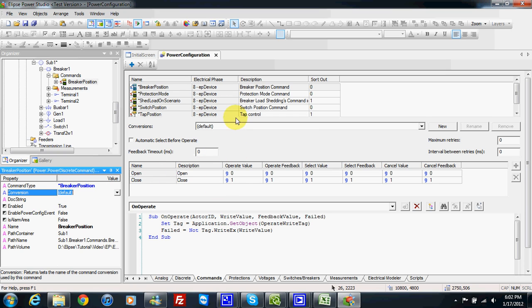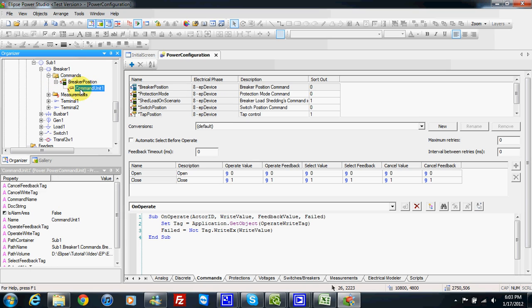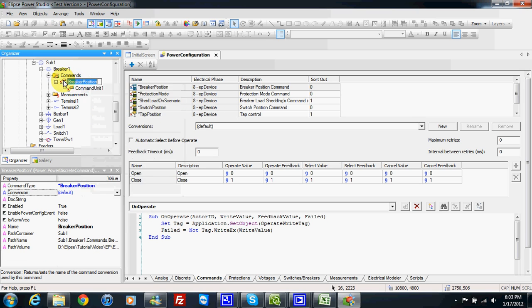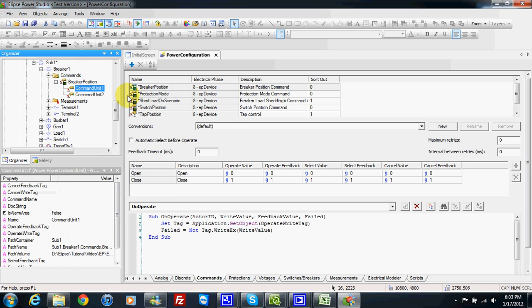For now we just select by default since we want to make a simulation. In breaker position I can also check inside — inside we have command units. In our case, when we send a command to the breaker position we want the breaker to open or to close, so we will have two command units. I right click and insert one more command unit. One command unit name will be open and one command unit name will be close.